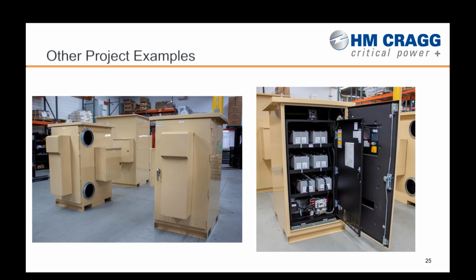Some of the challenges we had to face were that there was never a good source of utility power. We were instructed there'd be no shore power in any of the regions where these systems would be deployed. They would include input provisions for two 150 kW generators, and then a third input source for six Kubota generators, which could run in parallel. So this critical system was actually driven by three sources of generator input, which tells you how critical the equipment was to maintain that uptime.